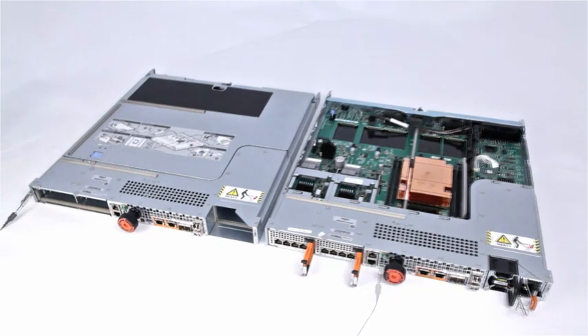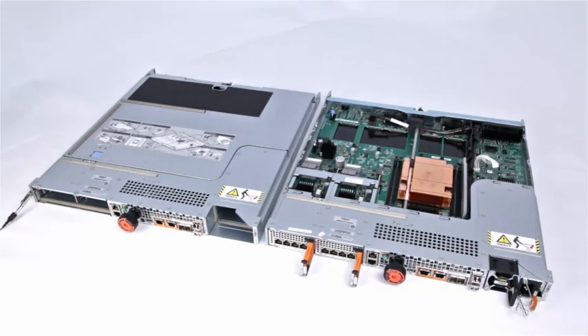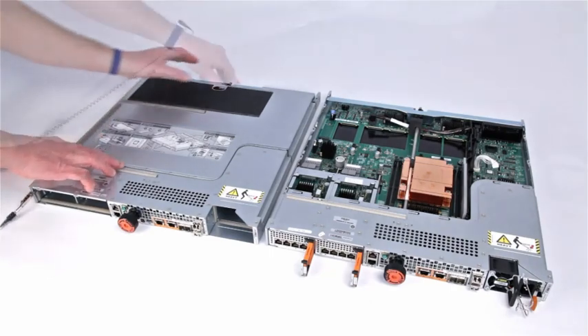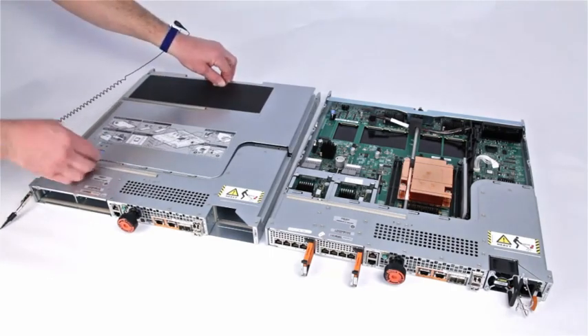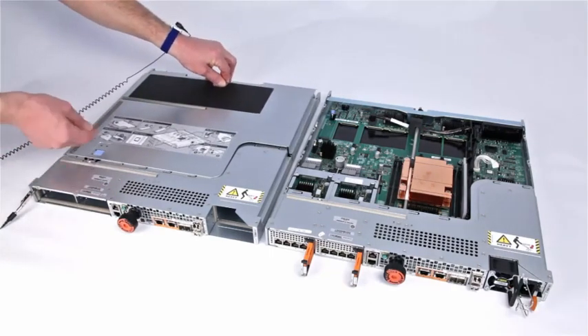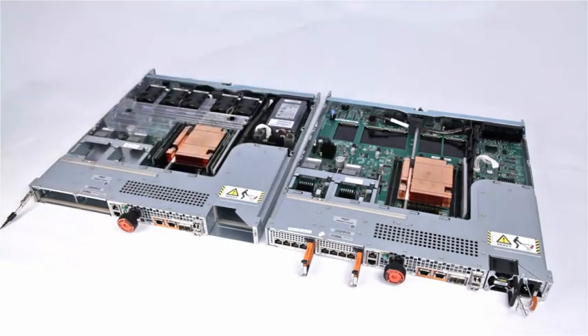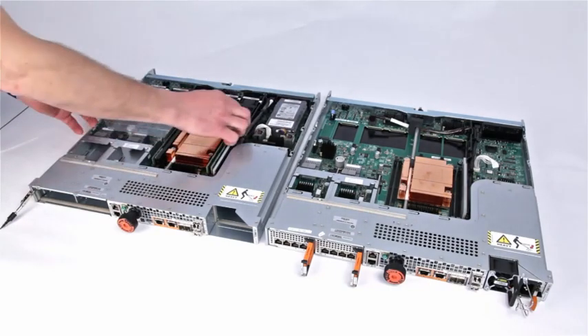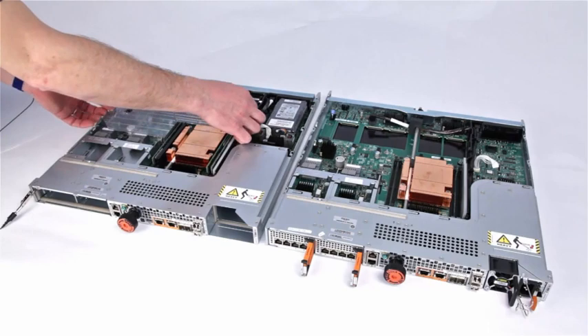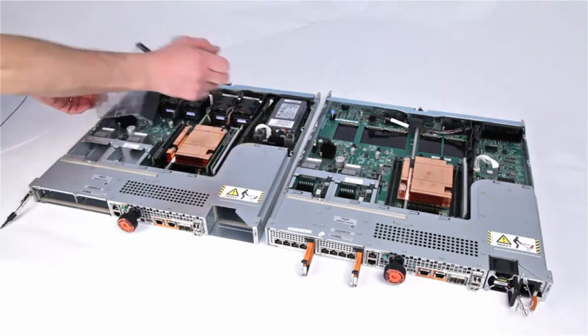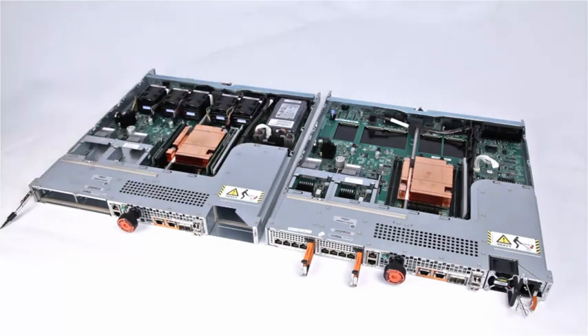Now we can start on the internal parts. While pushing down the blue release button, slide the top cover rearward approximately one half inch until it stops. Lift the top cover upward and remove it from the SP assembly. Press in on the tabs on both sides of the air flow baffle. Lift the air flow baffle upward and remove it from the SP.